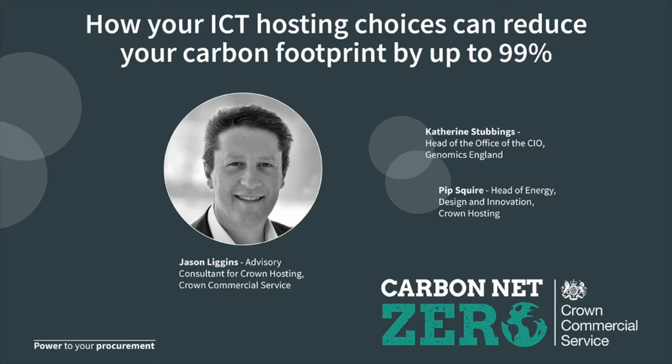Yeah, sure. In the broader sense, they're all data centers, in that they provide space for clusters of servers or communication equipment providing IT services to their users. I see the differences between the 3 falling into 3 broad areas. The first is size, the second is resilience, and the third is efficiency. Taking each in turn, in terms of size, a server room is typically a single room in a building that holds a number of servers. Normally it has a capacity of about, or maybe less than, 200 kilowatts, and they're often poorly ventilated and may only have a single power supply.